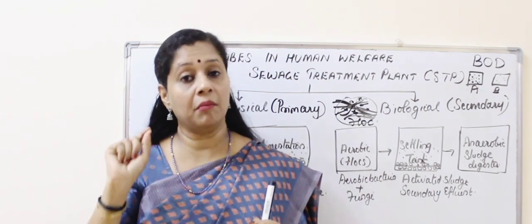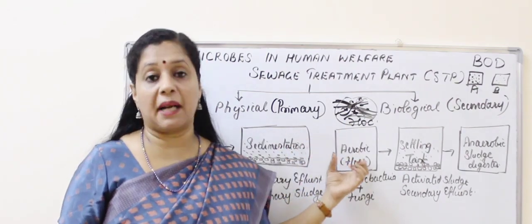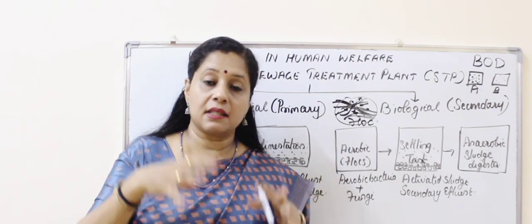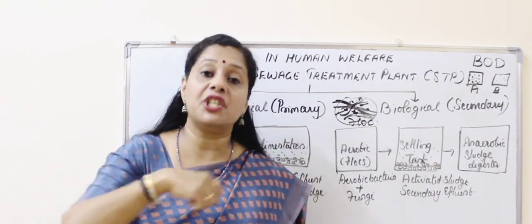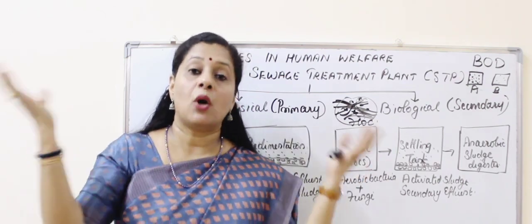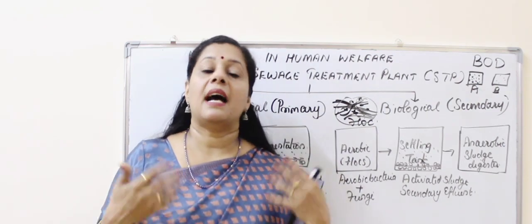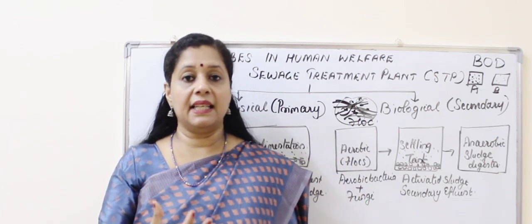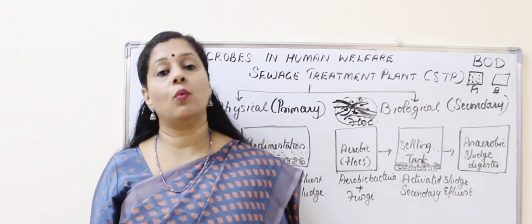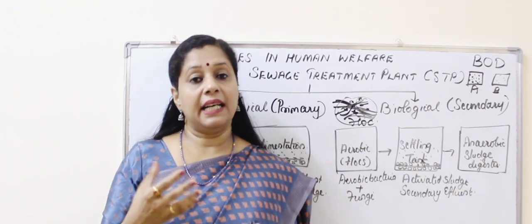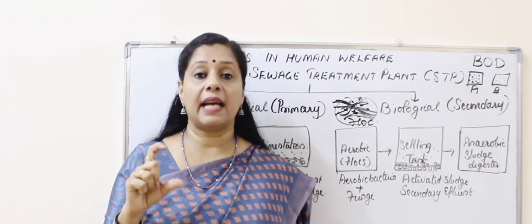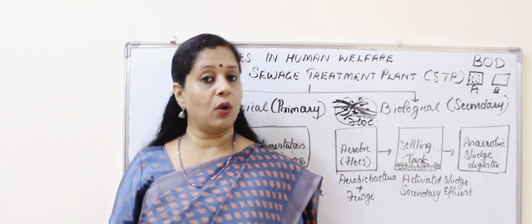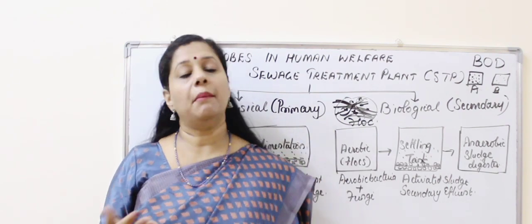Our idea is to reduce the BOD in this primary effluent. For that we use aerobic bacteria and fungi. Since aerobic bacteria and fungi are used in this tank, we do not keep it stagnant but perform continuous agitation. When we stir it continuously, oxygen comes inside and allows bacteria to multiply. As a result they deplete all the organic matter. We take samples to check the BOD quite frequently, and finally when the BOD level has come down and it is safe for releasing into the water body, we proceed. BOD can be defined as the amount of oxygen required for depleting all the organic matter present in one litre of water. Ecologists test pollution this way — if BOD is high, pollution is high; if BOD is less, pollution is less.